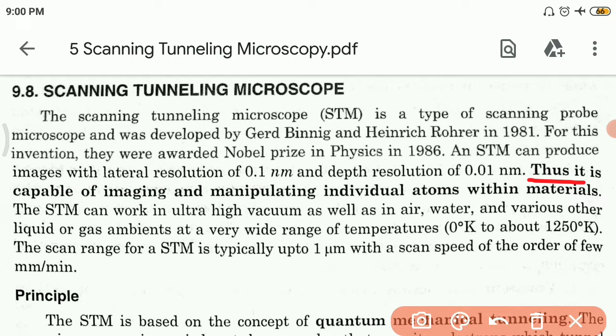Now it is capable of imaging and manipulating individual atoms within the materials. If we see the working area of this STM, it is capable of working in various conditions. STM can work in ultra high vacuum as well as in air, water and various other liquid and gas ambients, along with a very wide range of temperatures ranging from 0 Kelvin to about 1250 Kelvin. It has a scan range of typically up to 1 micrometer with a scan speed of the order of few millimeter per minute. So this means the STM has the capability of scanning a 1 micrometer area with a scan speed of the order of few millimeter per minute, right?